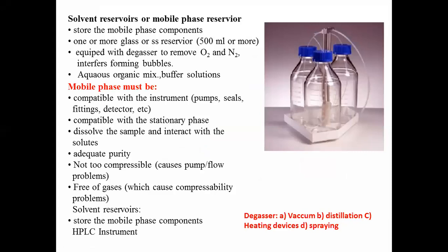Solvent reservoirs, or you may say that these are the mobile phase reservoirs. The function of the reservoirs is to store a sufficient amount of mobile phase for the complete experiment. So, storage of the mobile phase components. Generally these storage containers are one or more glass containers or made of stainless steel, having a capacity of say minimum 500 ml or more.